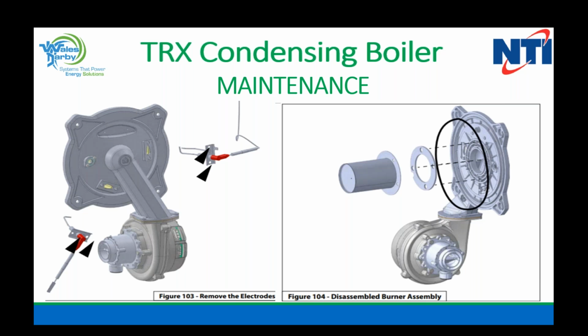Now, maintenance is an interesting thing. A lot of guys kind of shy away from doing this. And this is something that must be put forth to the homeowner when you install this type of boiler. Number one, most of these condensing boiler manufacturers are not going to warranty the equipment if no maintenance was done. So if there was a problem and it's due to a lack of maintenance, there's no warranty. And sometimes the contractors will say to me, well, Jim, the homeowner doesn't want it.